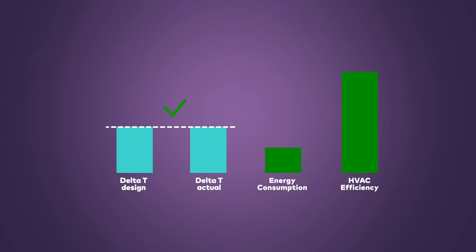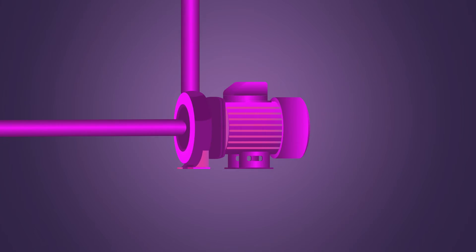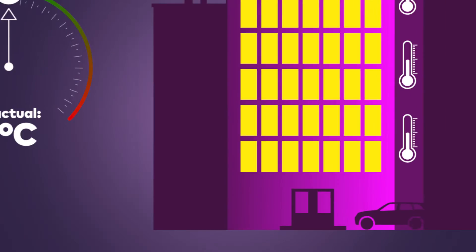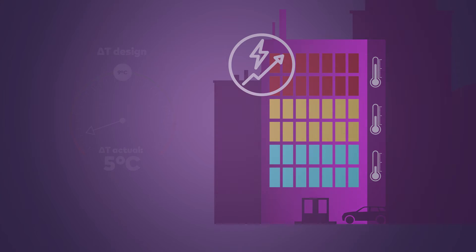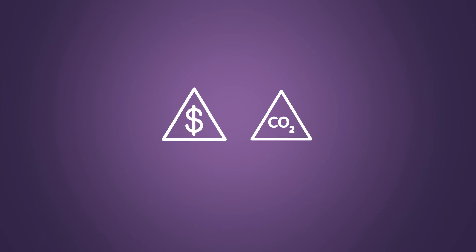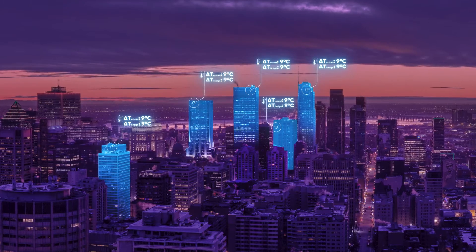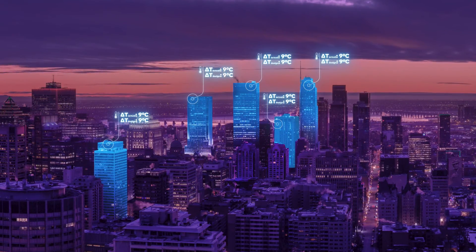When Delta-T is consistently lower than expected, we call it Low-Delta-T Syndrome. Some common causes of Low-Delta-T are oversized equipment and incorrect hydronic balancing. A system suffering from Low-Delta-T Syndrome requires more energy to achieve the desired temperature levels, leading to increased energy bills and a higher carbon footprint. This is detrimental for any building type, but particularly for district cooling applications.